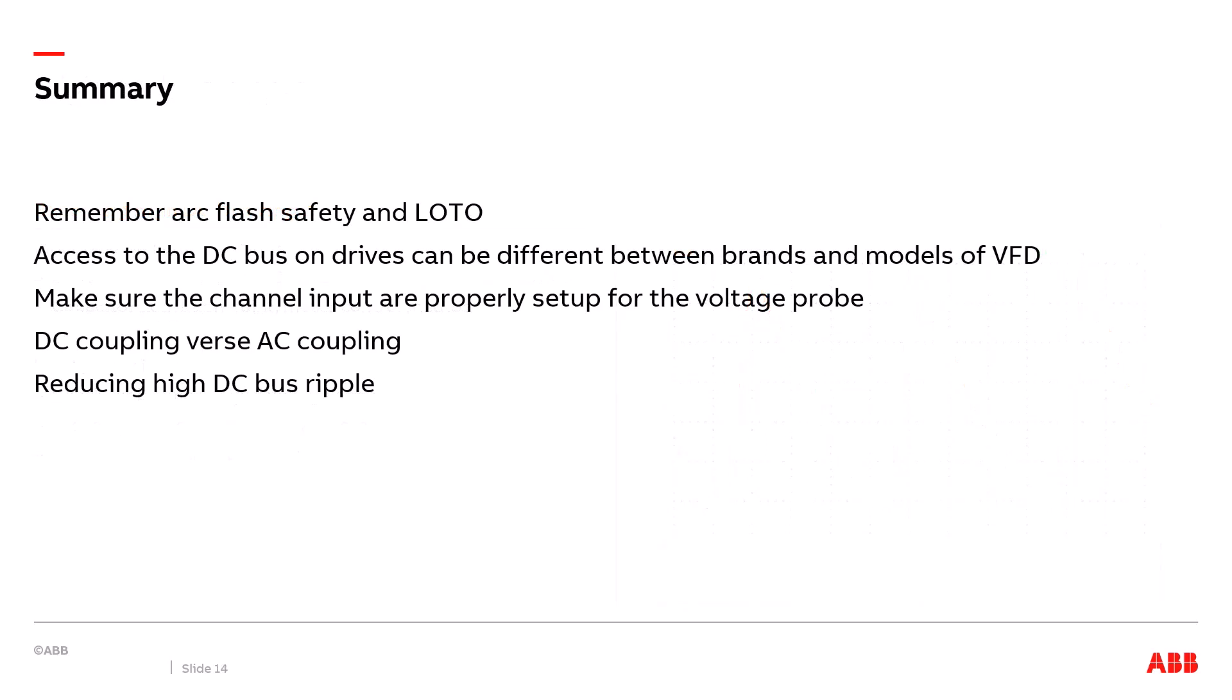All right let's summarize what we've learned in this presentation. First off from an electrical safety standpoint remember to wait five minutes once power has been removed before making any connections to the VFD. Depending on the model and brand of VFD the access to the DC bus can be different so make sure to review a manual for proper terminal locations if necessary. When we set up a scope for the voltage probe we want to make sure that we set it up correctly so that the signal will be scaled correctly on the scope. We learned the differences between DC coupling and AC coupling. AC coupling you can see the voltage ripple much easier compared to DC coupling and if you do have a high peak to peak voltage ripple on a DC bus depending on the cause there can be different solutions. Some of them can be just adjusting some parameter settings in the drive while other ones may require additional hardware such as a line reactor to resolve a DC bus ripple issue.